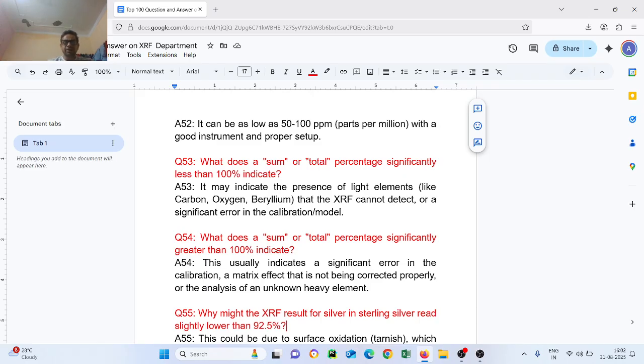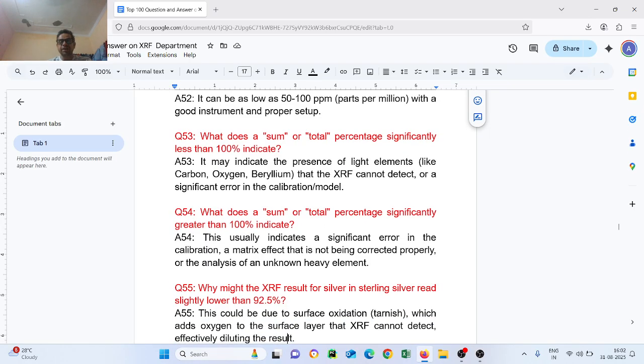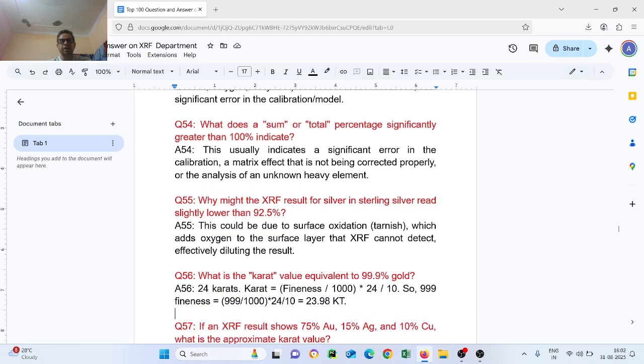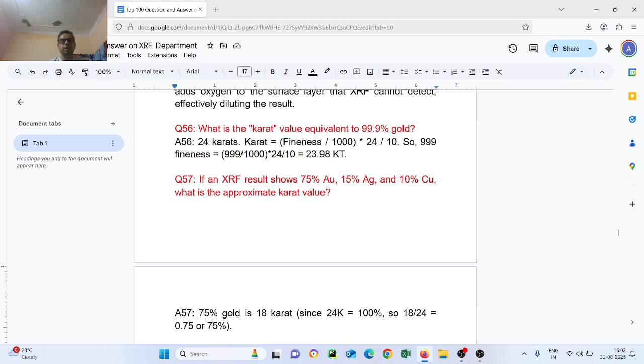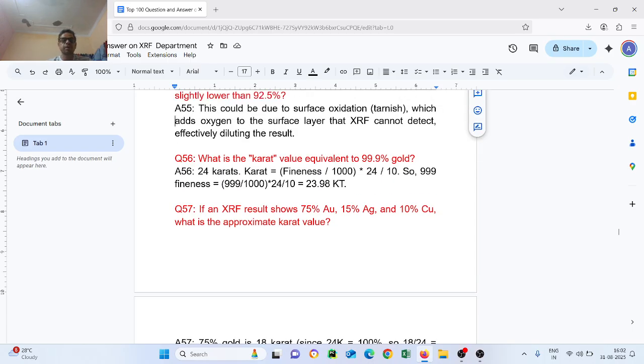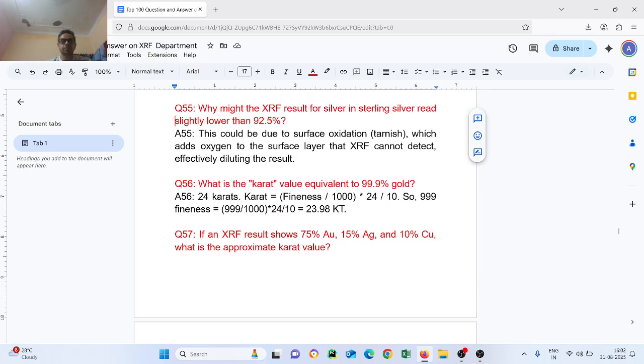Why might the XRF result for silver in sterling silver read slightly lower than 92.5%? Answer: this could be due to surface oxidation tarnish, which adds oxygen to the surface layer that XRF cannot detect effectively diluting the result.